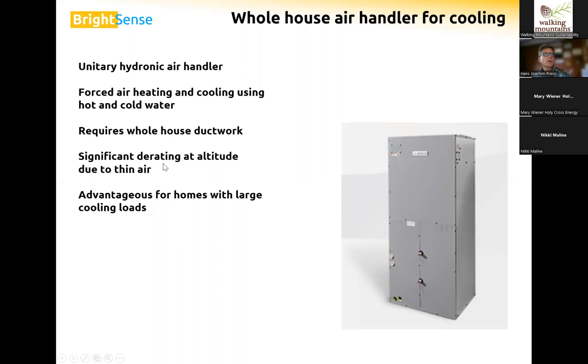It's significantly derated because of altitude, the thin air. The higher you go up, the thinner the air, and when you're moving air at this scale, you probably lose 20% of its capacity because of that altitude derating. That's why you don't see those too much at higher altitudes, but those are typically used in larger homes with significant cooling loads because of a lot of glazing that brings in solar heat gain.